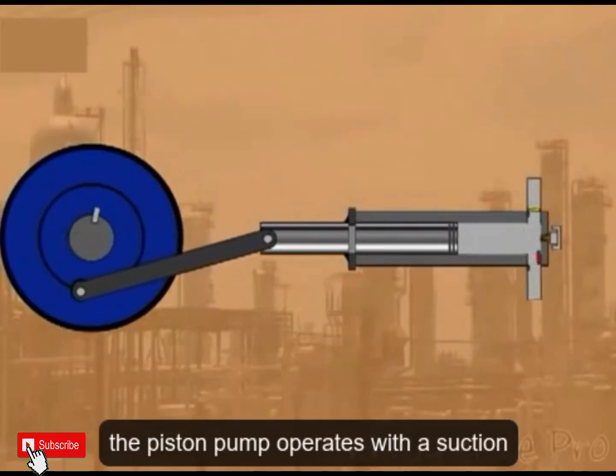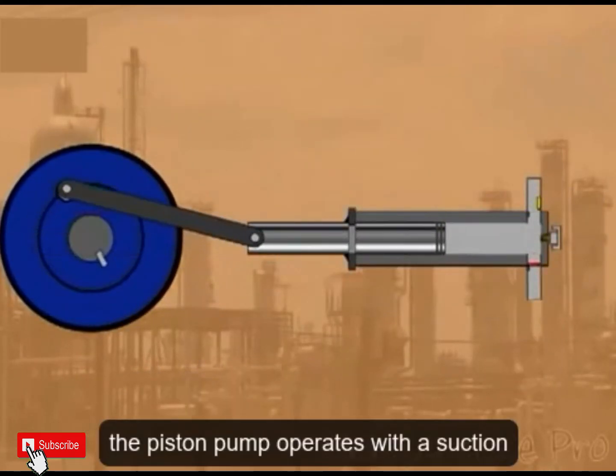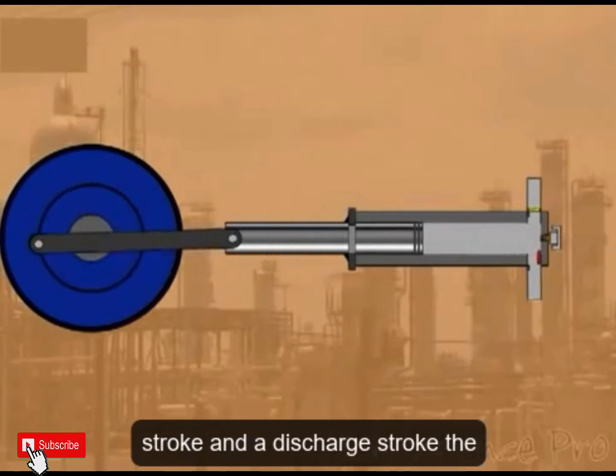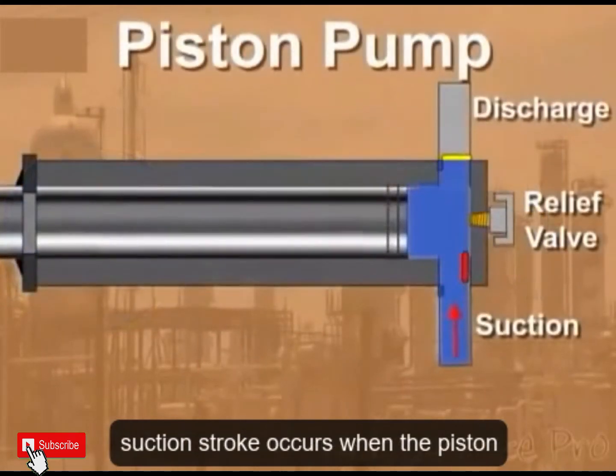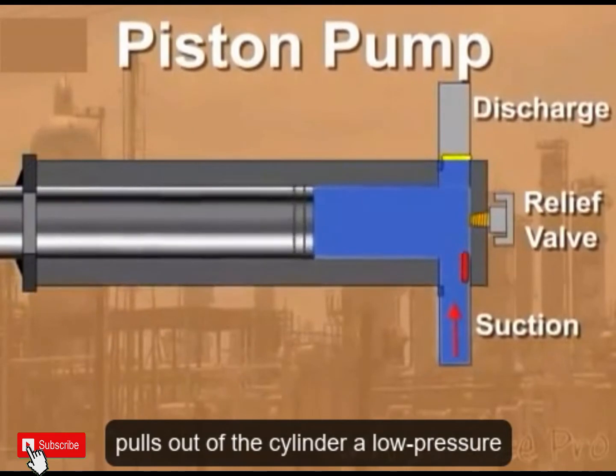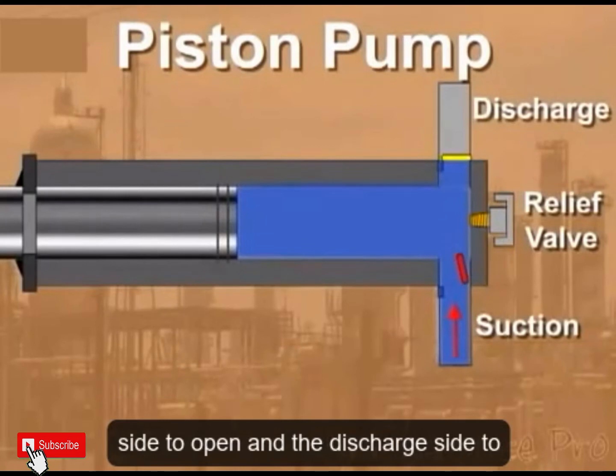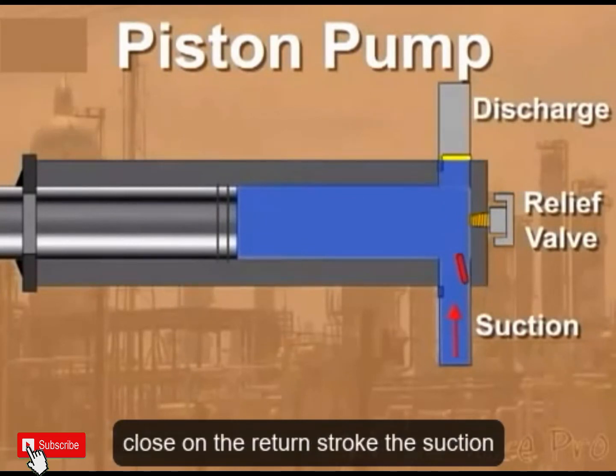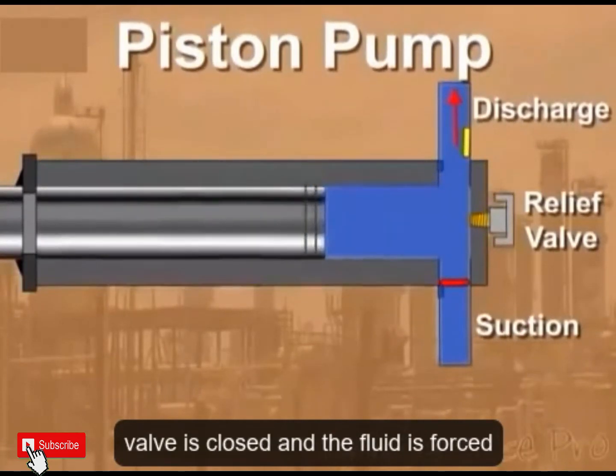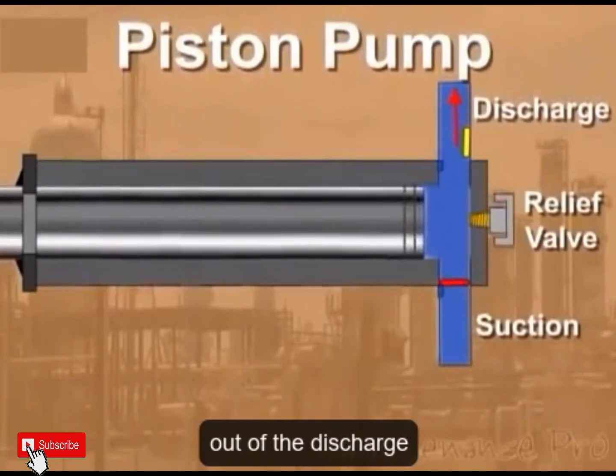The piston pump operates with a suction stroke and a discharge stroke. The suction stroke occurs when the piston pulls out of the cylinder, creating a low pressure vacuum that causes the suction side to open and the discharge side to close. On the return stroke, the suction valve is closed and the fluid is forced out of the discharge.